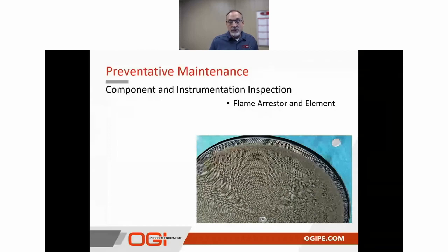So we're going to start with the flame arrestor. Here we're going to confirm that the element is not plugged, which is a common fault causing problems with the combustion process of the heater. So in this case, we're going to look for dirt, possibly cottonwood, even bird nests. We've seen bird nests and mice nests actually developing in a flame arrestor.